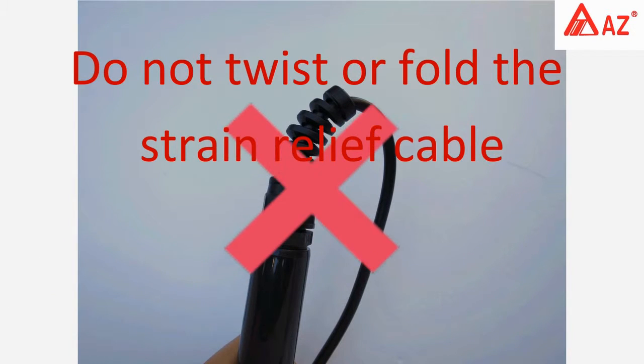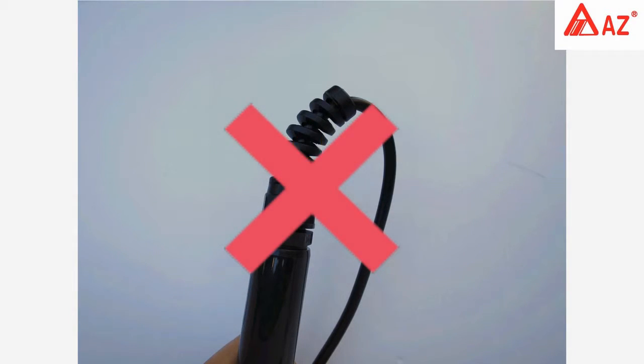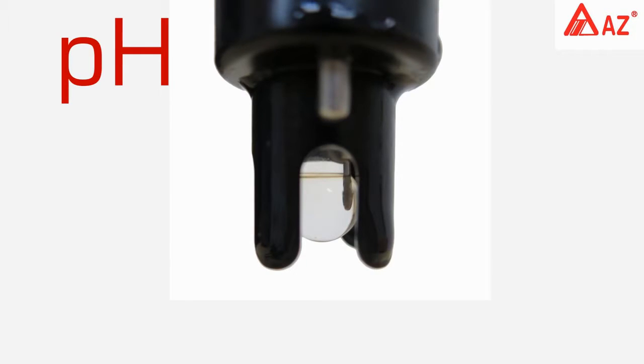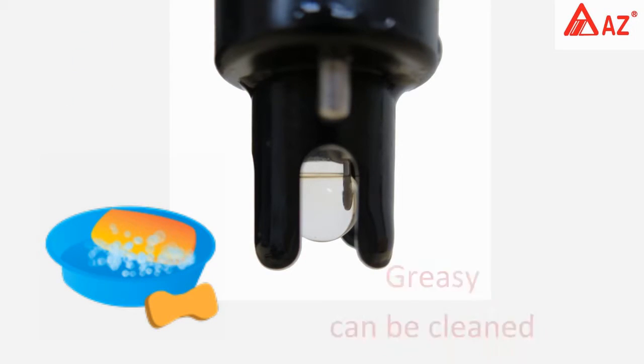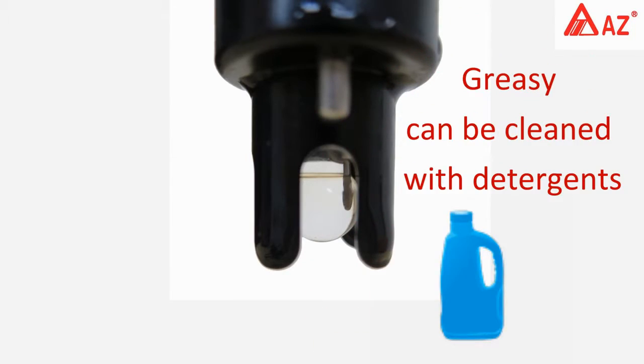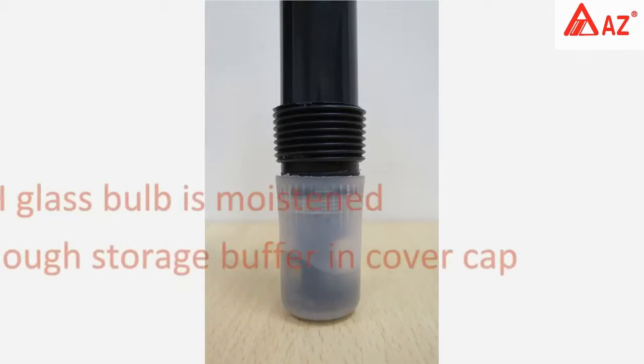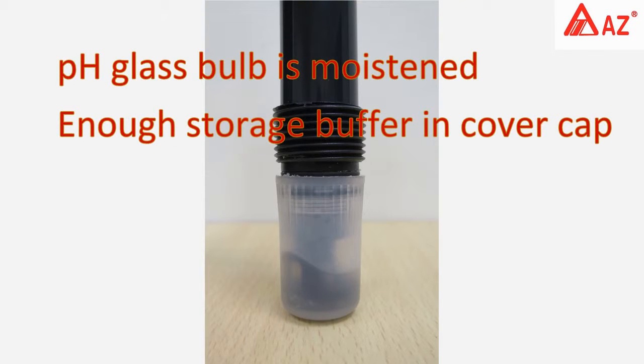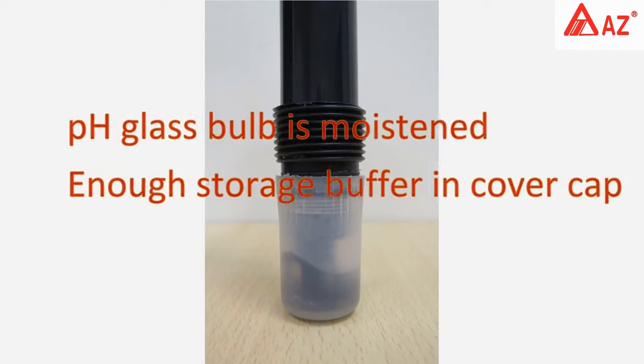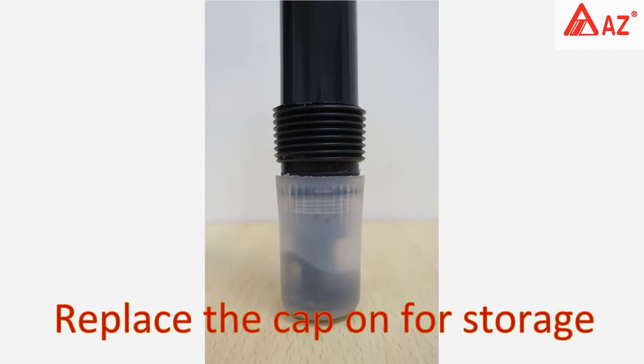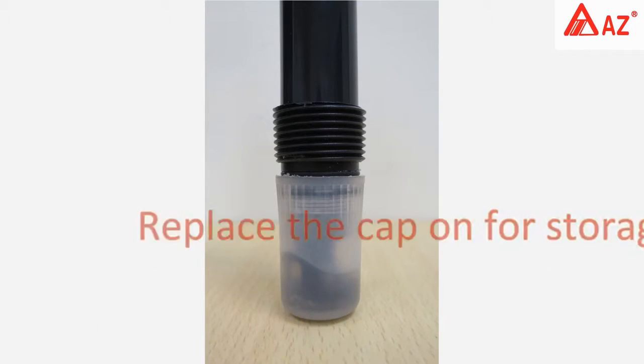Do not twist or fold the strain relief cable. If the pH probe is stained with grease or dirt, clean it with neutral detergent. Make sure the pH glass bulb is moistened at all times, and there is enough storage buffer in the cover cap. Replace the electrode cap for storage.